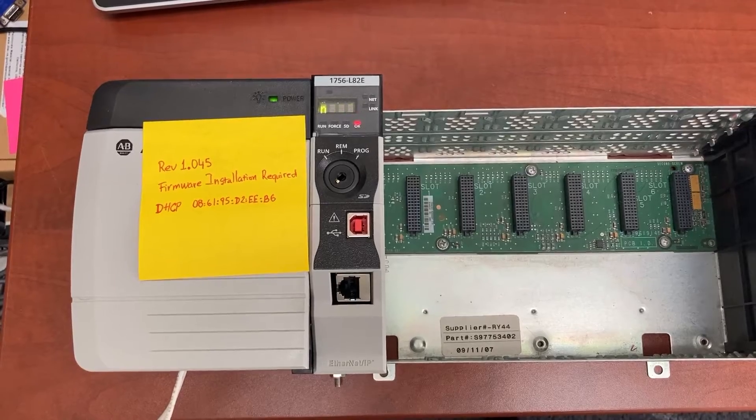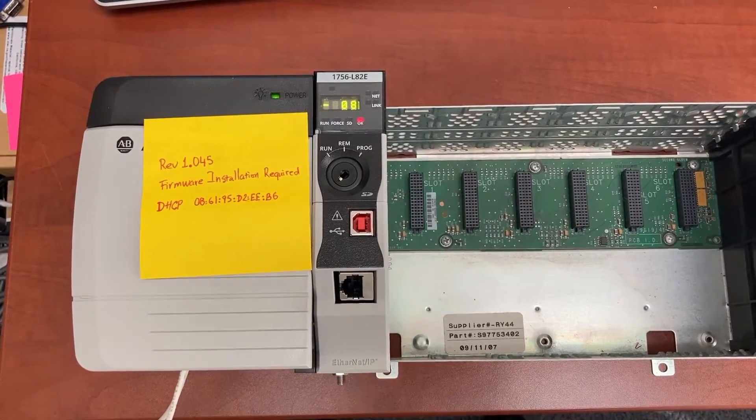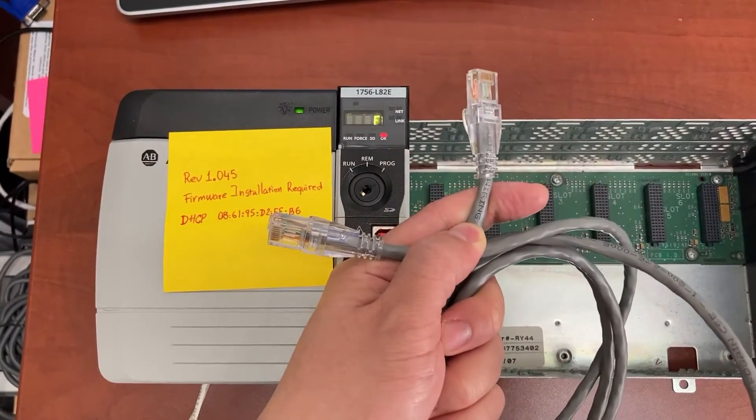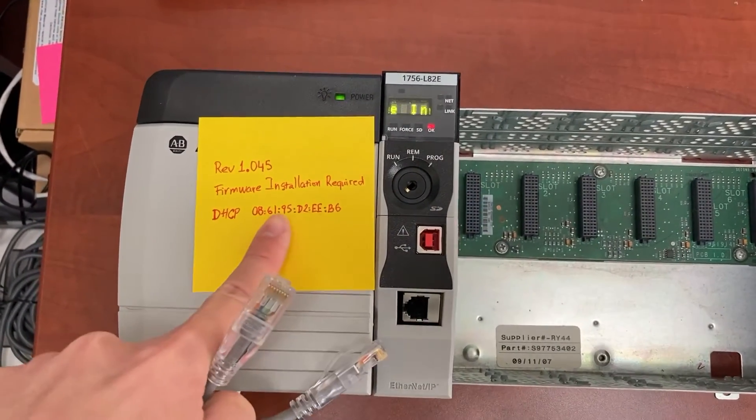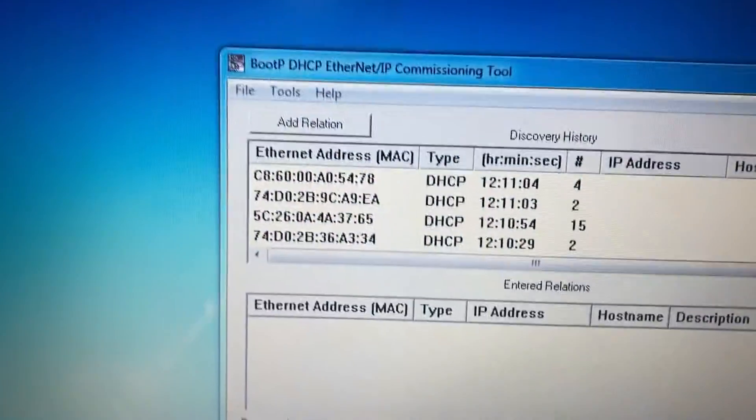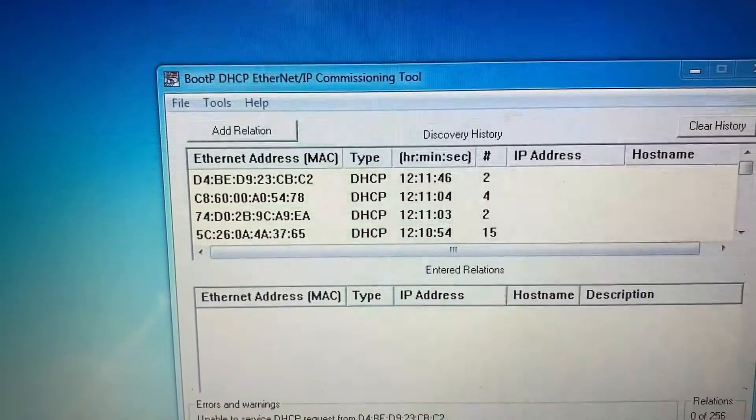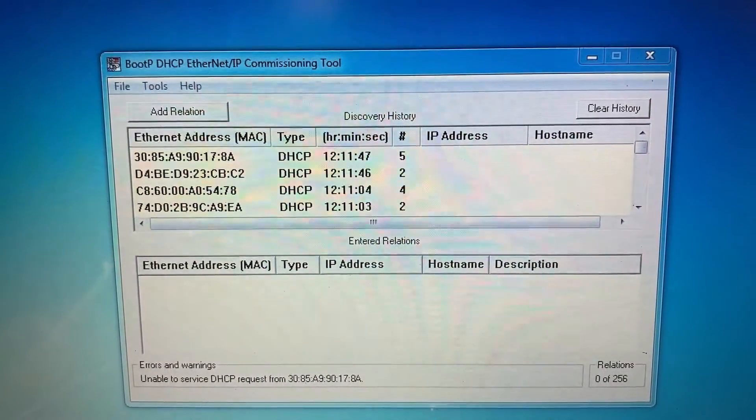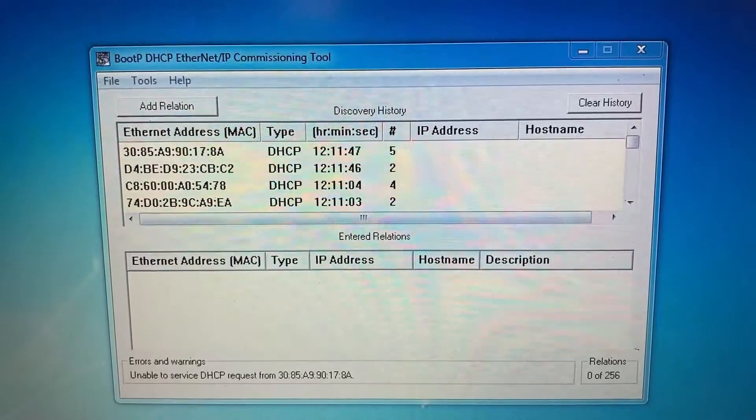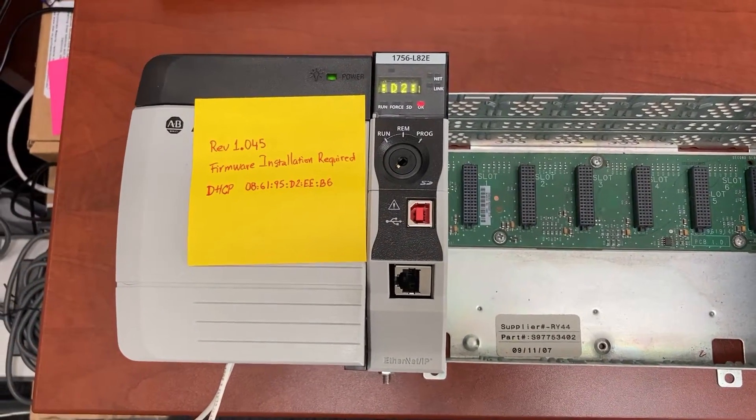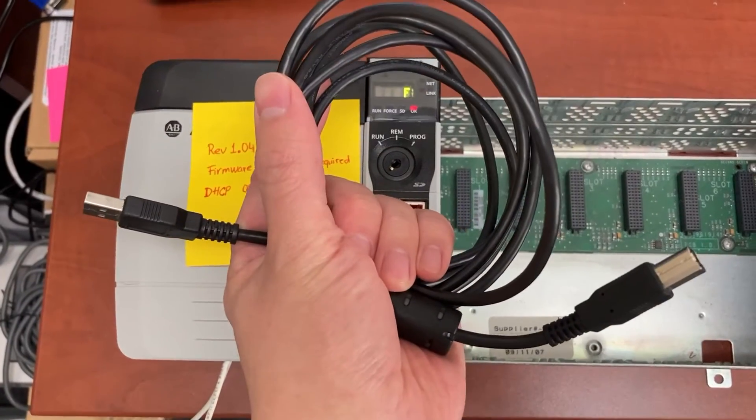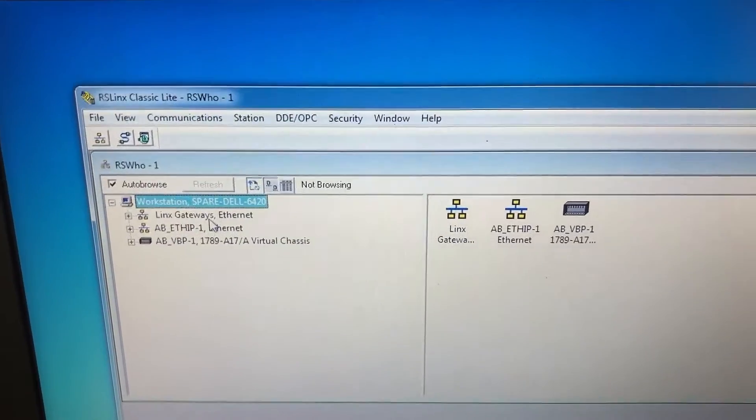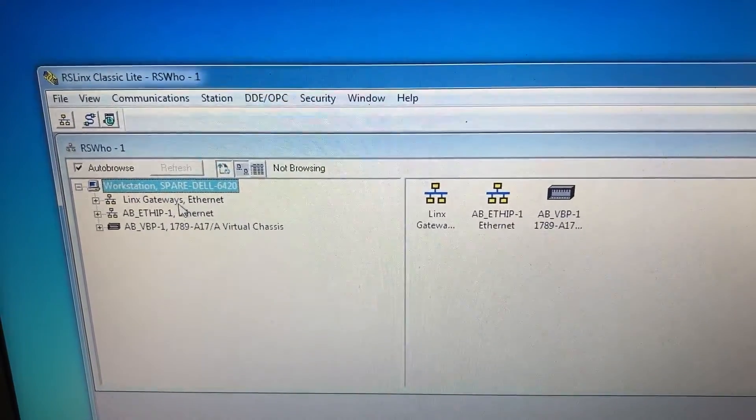There are two ways to set up the IP address for the controller. The first one is to use the Ethernet CAT5 cable with the provided MAC address and BootP DHCP Ethernet IP commissioning tool to find the controller and set the IP address. The second one is to use the USB cable with RSLinx Classic to set the IP address to the controller.